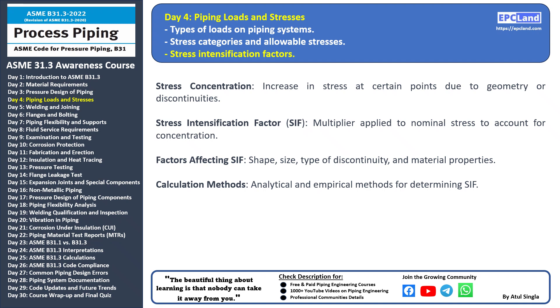Stress intensification factors play a crucial role in understanding how stress concentrates at specific points in a piping system. Stress concentration — imagine bending a paperclip; you'll notice that the stress is higher at the bends. This increase in stress at certain points due to changes in geometry or the presence of discontinuities like welds, fittings, or changes in pipe size is known as stress concentration.